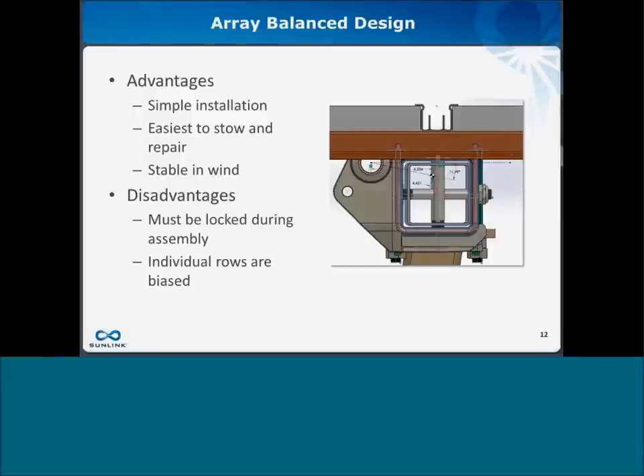The last type of configuration we discuss is what I call an array balance design. In this case, the bearing is not above, below, or around the torque tube, it's off to one side. What that creates is an individual tracker row that's off balance and wants to go in one direction. To make a balanced array, you simply put essentially equal numbers of rows and mirror image them, so one half of the array wants to go one way, one half the other, and they're linked together so they're essentially having a bit of a tug of war. It keeps the entire array balanced.